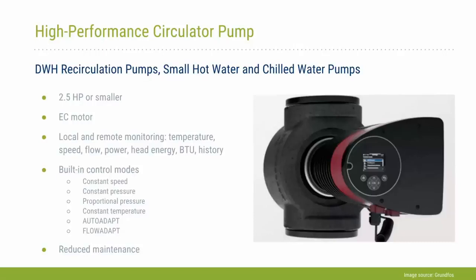As Jay noted, I think one of the big technological advances or innovations with this technology is that we're moving from an older, inefficient induction motor to a modern ECM motor. The ECM motor itself has integrated power electronics that allow integrated speed control so that the pump can ramp up and down without having to have a secondary variable frequency drive. This pump also has a number of pre-programmed control modes, which you'll see there.